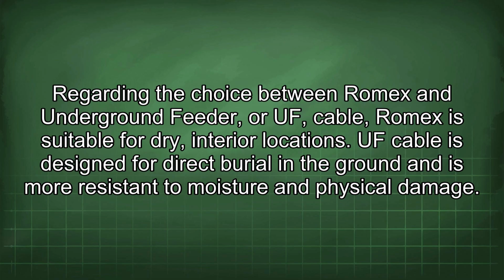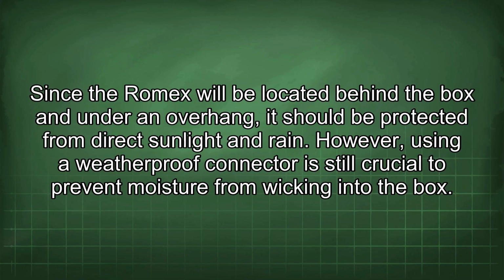Regarding the choice between Romex and underground feeder, or UF cable, Romex is suitable for dry, interior locations. UF cable is designed for direct burial in the ground and is more resistant to moisture and physical damage. Since the Romex will be located behind the box and under an overhang, it should be protected from direct sunlight and rain. However, using a weatherproof connector is still crucial to prevent moisture from wicking into the box.